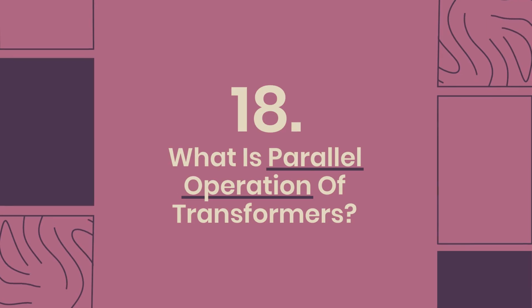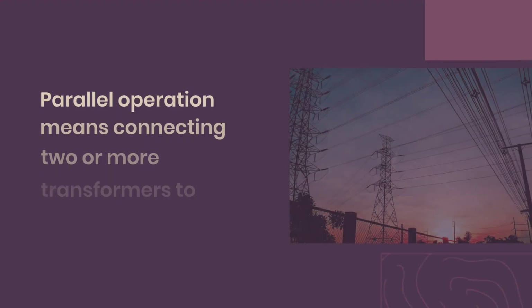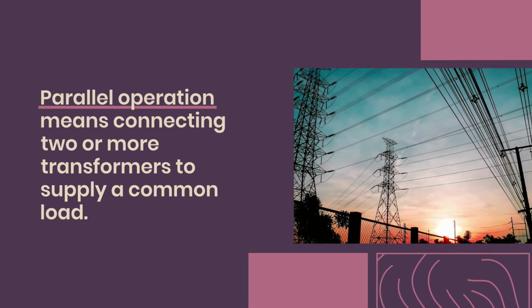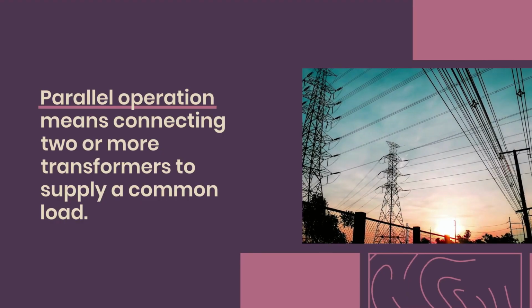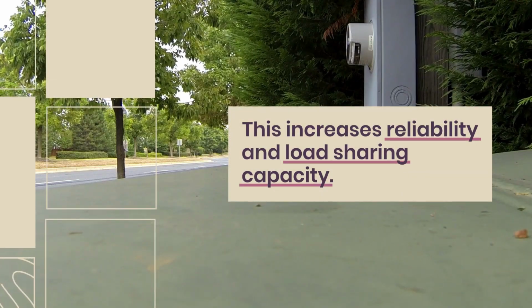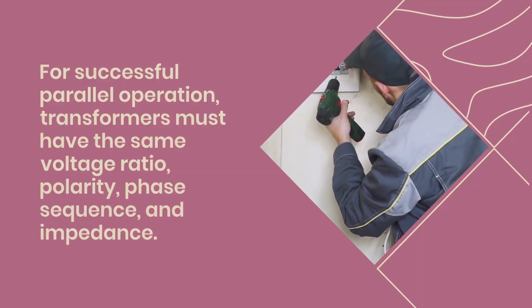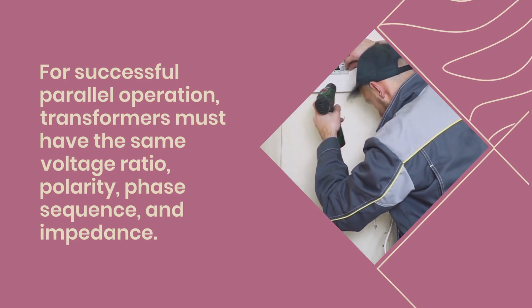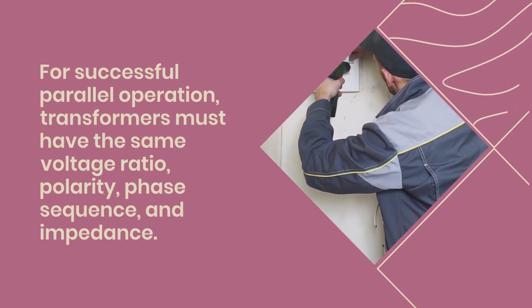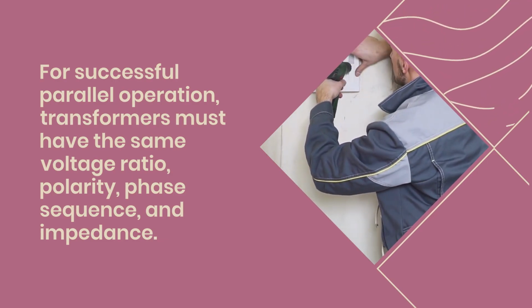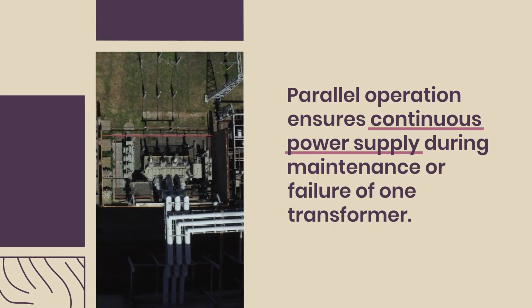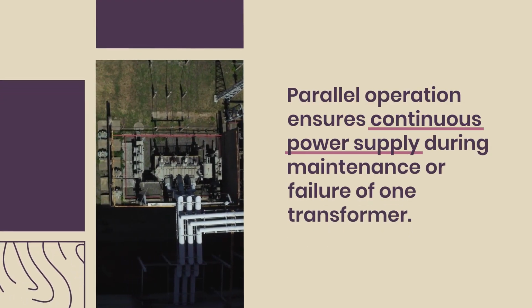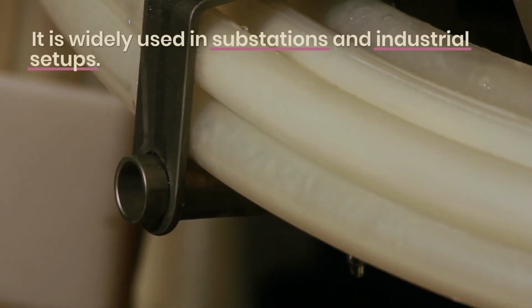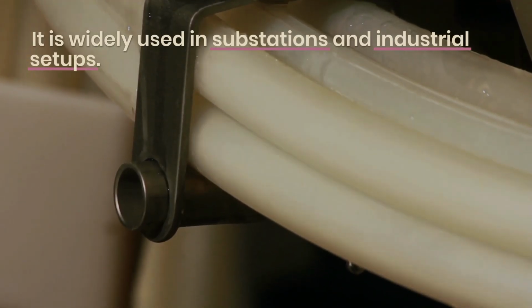18. What is parallel operation of transformers? Parallel operation means connecting two or more transformers to supply a common load. This increases reliability and load sharing capacity. For successful parallel operation, transformers must have the same voltage ratio, polarity, phase sequence, and impedance. Proper load sharing prevents overloading. Parallel operation ensures continuous power supply during maintenance or failure of one transformer. It is widely used in substations and industrial setups.